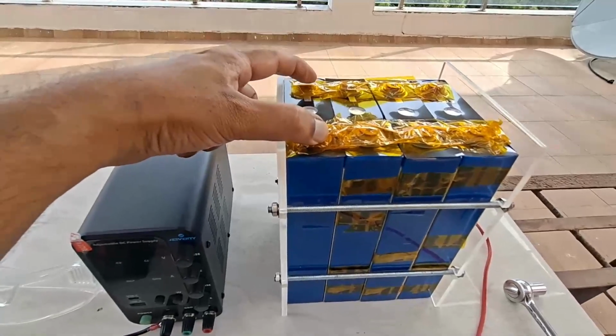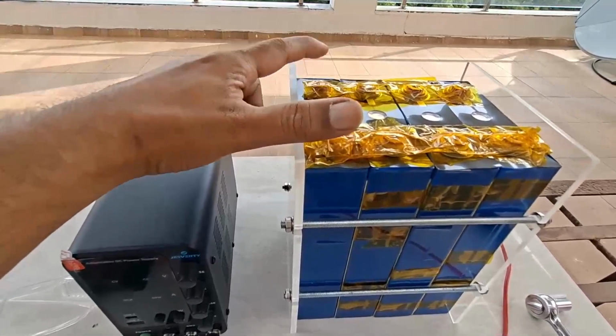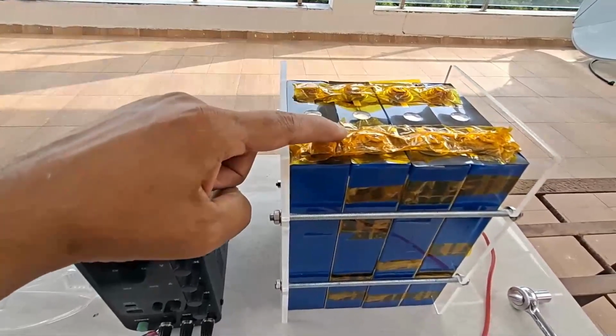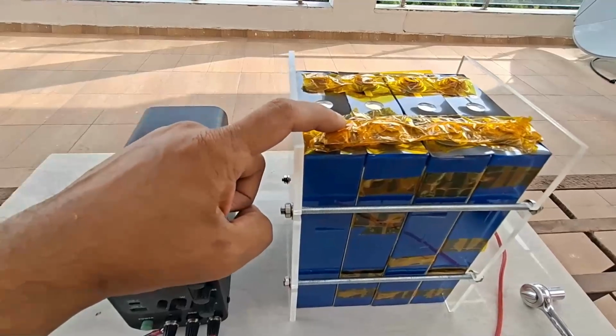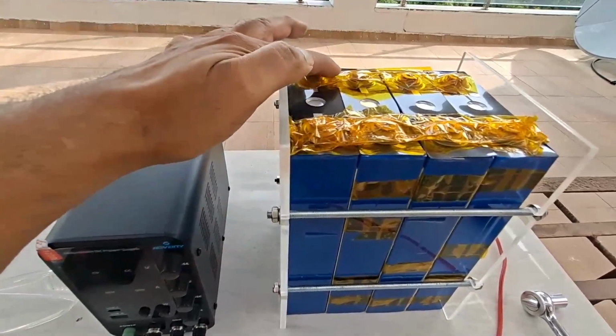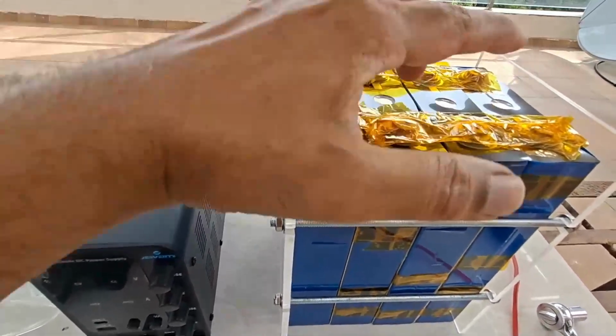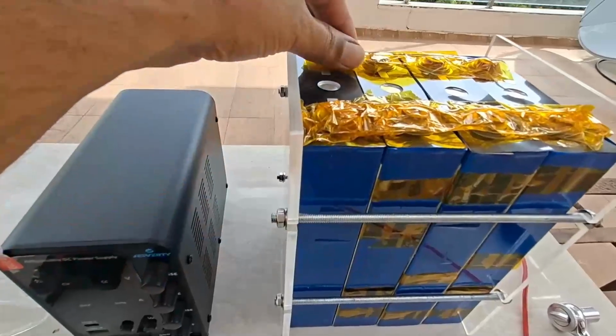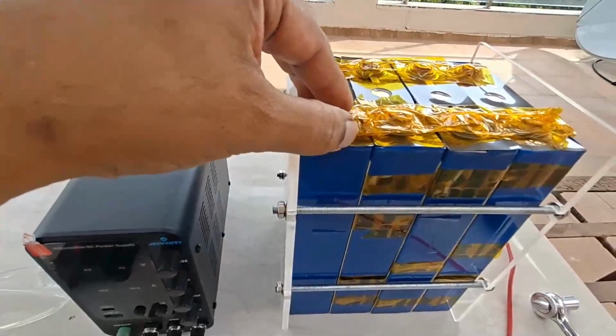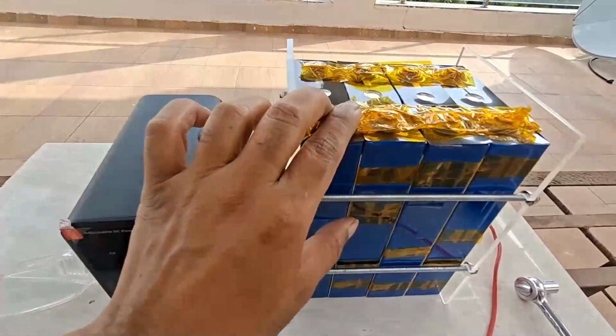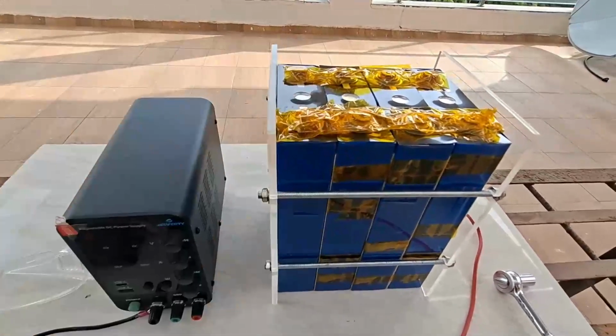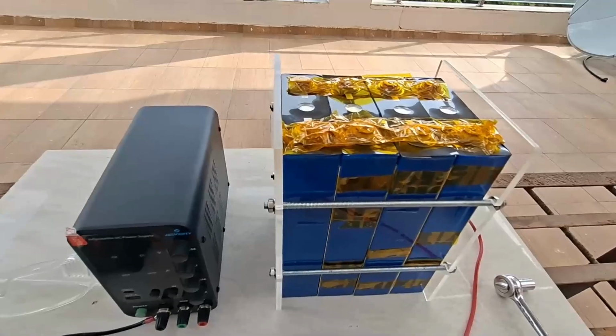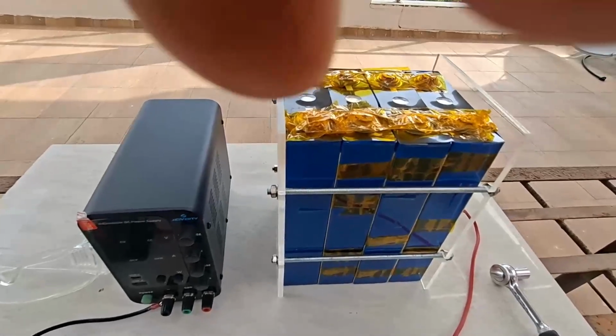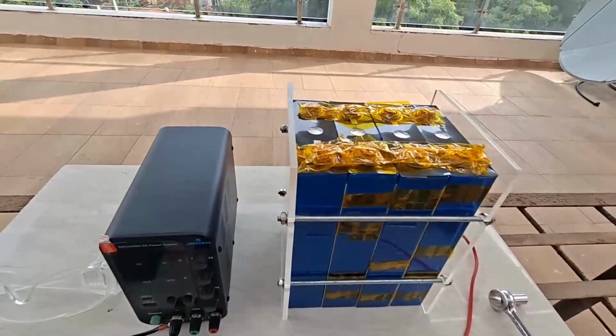If you are, let's say, putting a screw on these terminals, it is best to tape up the other side. Once you're done making whatever connections you want on these terminals, and now you want to start working here, tape up this side. Then you can remove the tape on this side and start working on it. The reason is simple: at any stage, you are not exposing the positive and negative terminals simultaneously.